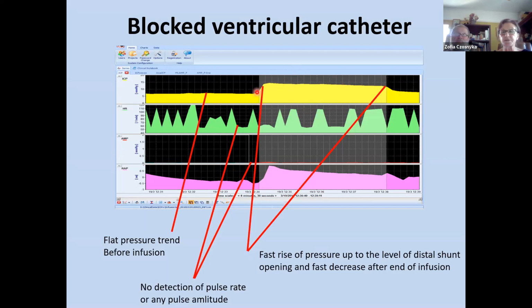We observe the very steep response to the start of the infusion, which is due to the very small compliance of only the isolated shunt chamber. It is important to be aware that the measurement here represents the pressure in the isolated shunt chamber, and doesn't provide any information about the real patient's ICP.